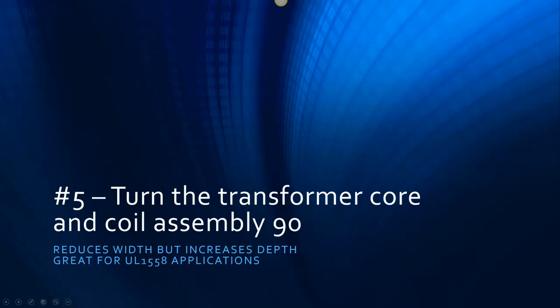We used this trick on several projects. About 8 times out of 10, you will save linear width by rotating the core and coil assembly of the transformer 90 degrees. And this is usually in a dry type transformer. A dry type transformer, until you get to about 3,000 kVA, is longer than it is deep.